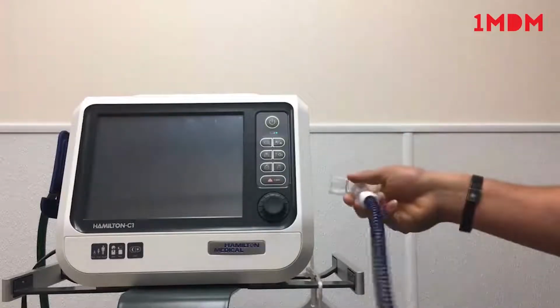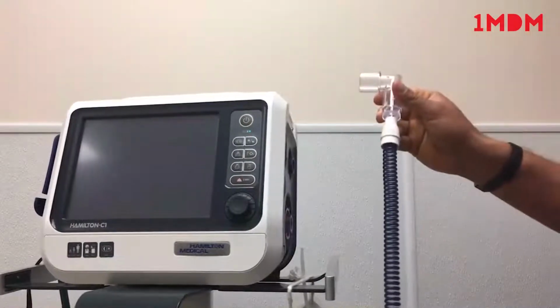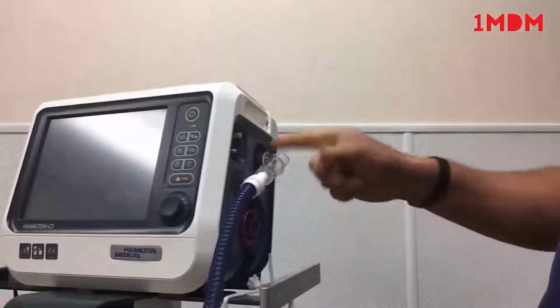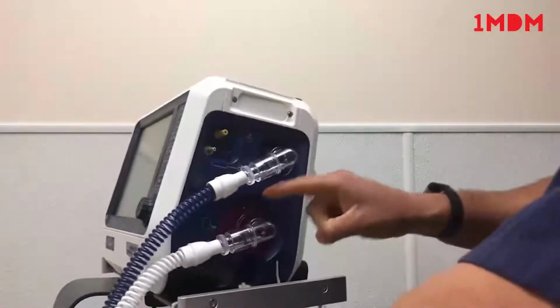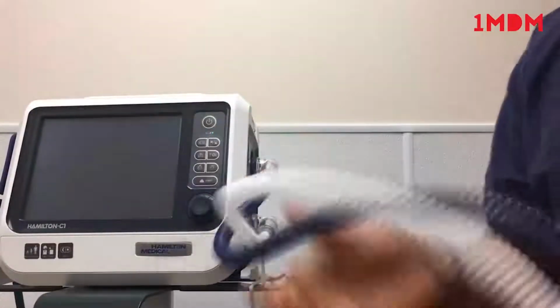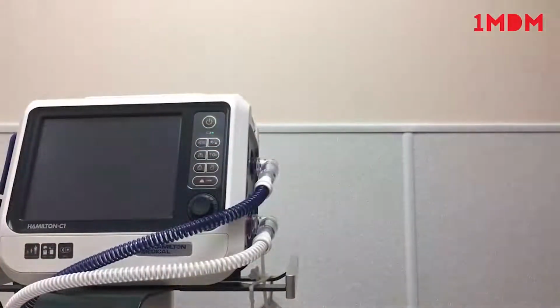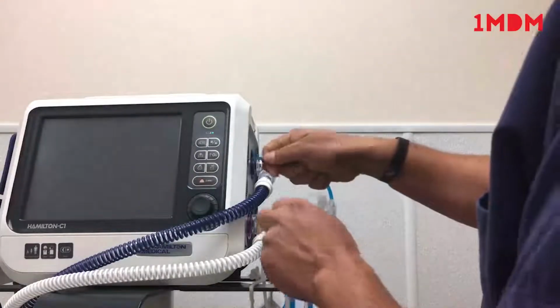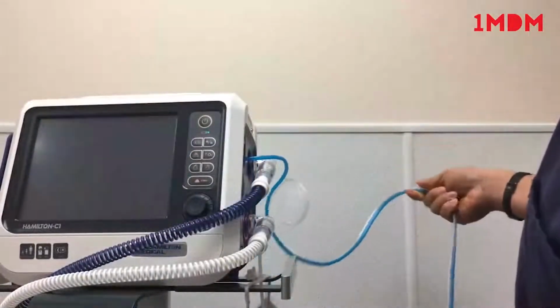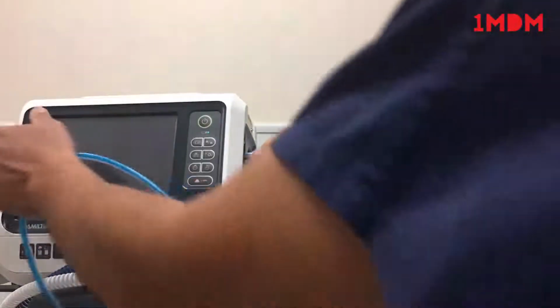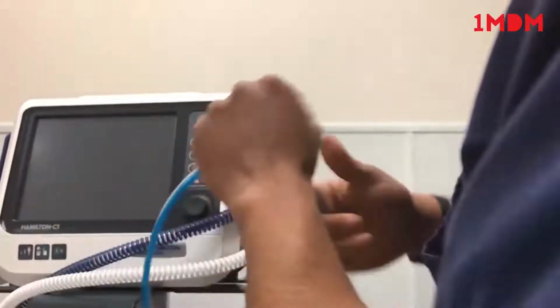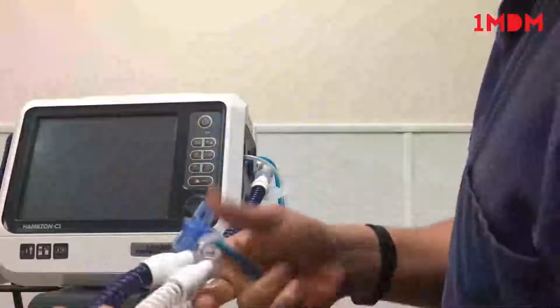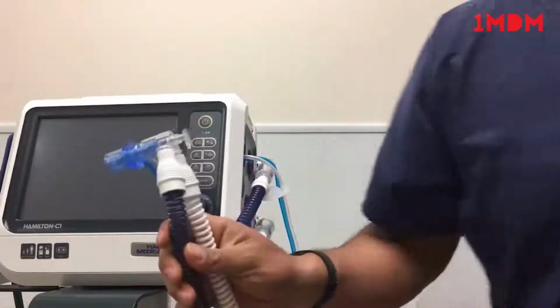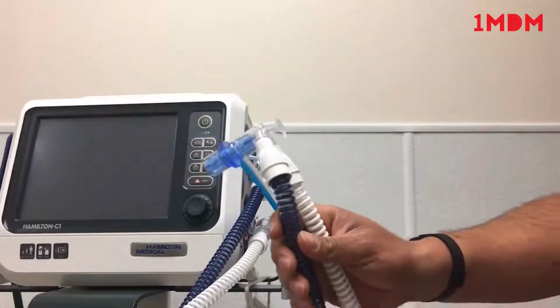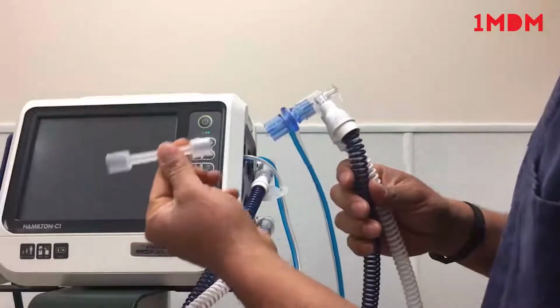Now go ahead and assemble the circuit by placing the inspiratory valve. You're going to match that blue color to blue color, and the exhalation valve is going to go to your white limb, and that's going to be attached to your pink expiratory valve. Once that's attached, you're going to attach your flow sensor. Make sure you only use the flow sensor that comes inside the neonate circuit. Make sure you don't use the adult flow sensor. So once everything is attached, one very crucial and important piece of this puzzle is going to be the wishbone. This is used to essentially calibrate your circuit.